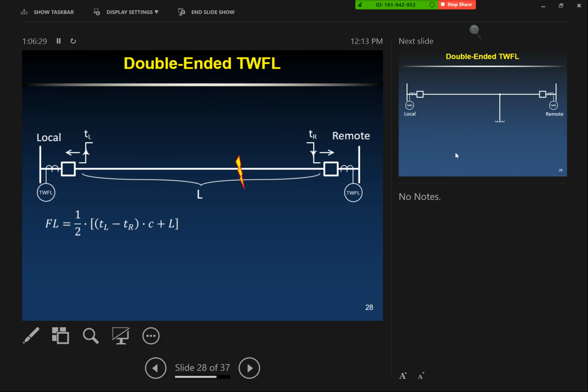So are there any cases where the traveling wave fault locator at the local versus the remote will have two disparate times? Meaning if I use a 0.985, if that's what I calculate after having closed the local end into an open remote, am I going to get that exact same time constant closing the remote into an open local? You should get exactly the same time, yeah. So when you guys are commissioning it, are you only doing it from one end and applying that same constant in both relays? Yeah, exactly. Usually for us, especially on a line like this, you have a bunch of taps. I can't get a clearance to de-energize the line, so I'm just mapping the breaker seal into the SER mask, capturing an event on the line test, and usually we're just line testing from one end. So I usually just get that data on one end anyway, and I just assume it's going to be the same, yeah.